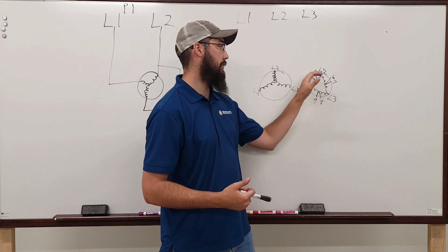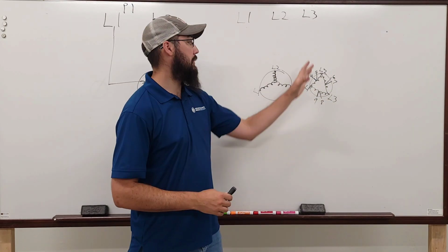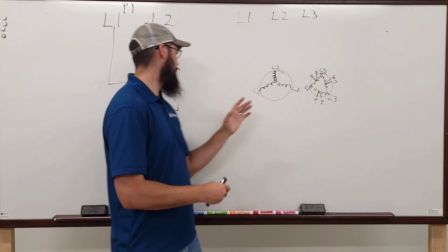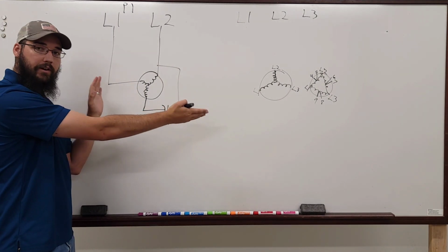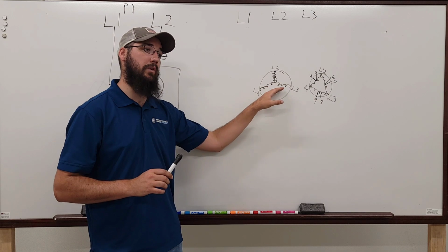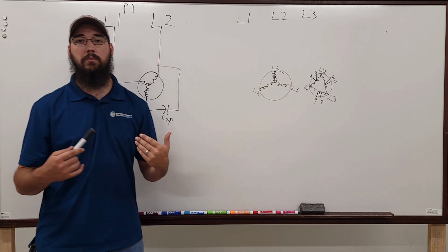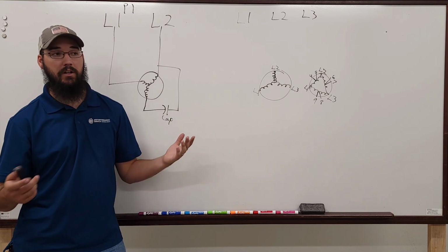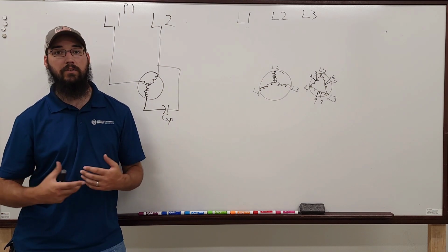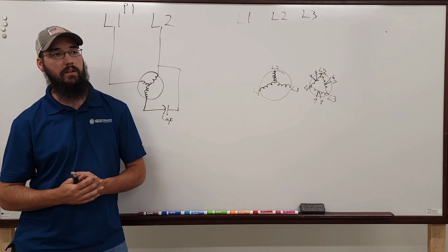And that configures this winding to be able to operate within that parameter. This is your primary difference. You're talking very different winding configurations at this point. Most of the time, the only time we will see these is typically on compressors. So specifically, you start getting into chiller size equipment or the Carlyle 06D specifically.